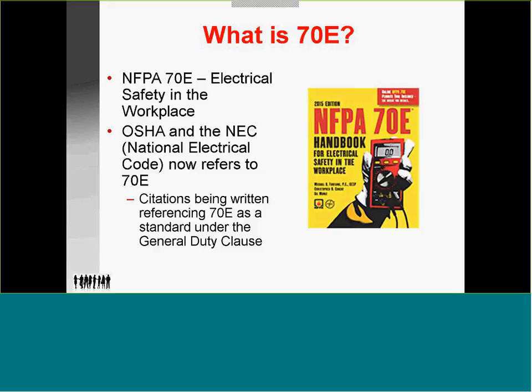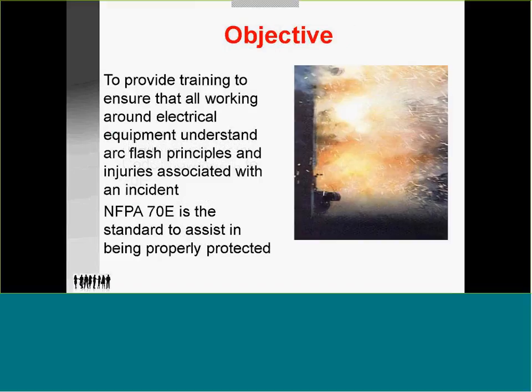70E was adopted by OSHA in 2009 as the minimum working standard. They set a general duty clause for failure to follow a nationally recognized standard. This edition is 2015, and I would recommend anybody working with electrical have a handbook. The code is one thing, but the handbook explains it in detail and the interpretation of it.